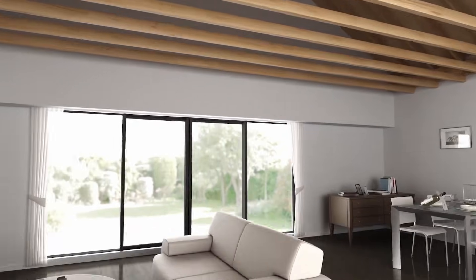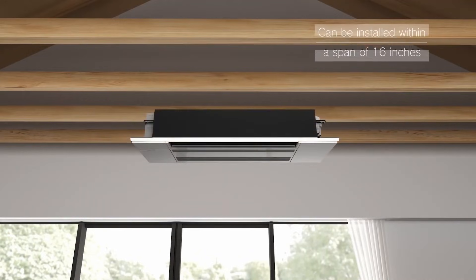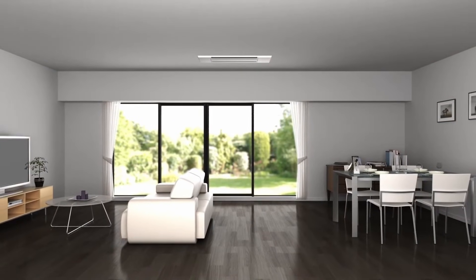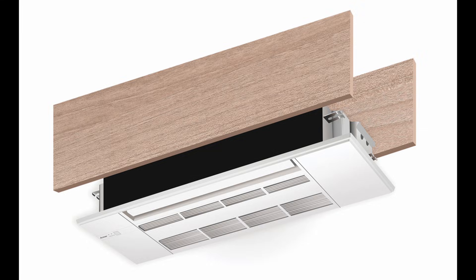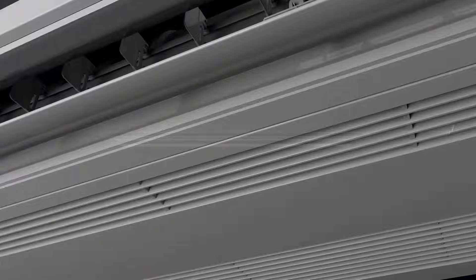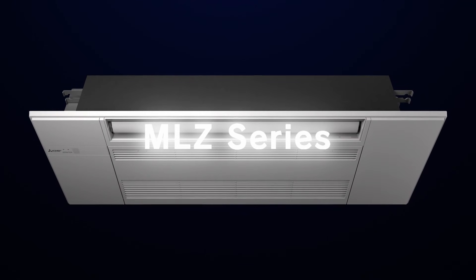1. Size and Fit. The Mitsubishi MLZ EasyFit was designed to fit the most common joists in the United States, 16 inches on center. The unique dimensions of U.S. joists make most ceiling cassette projects more difficult and uneconomical to install for residential applications. Most manufacturers only produce ceiling cassettes that are 24 by 24 inches or 30 by 30 inches. Mitsubishi was the first to introduce a unit that fits between 16-inch joists. The width is 16 and 11/16 inches and the length is 38 and 1/16 inches.